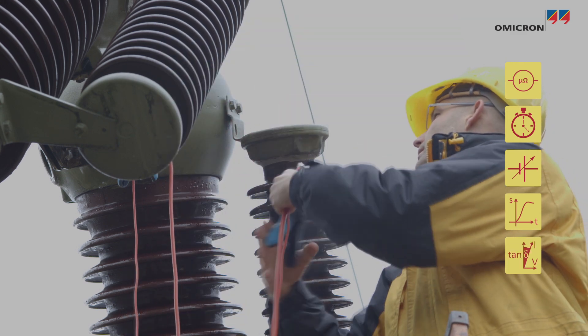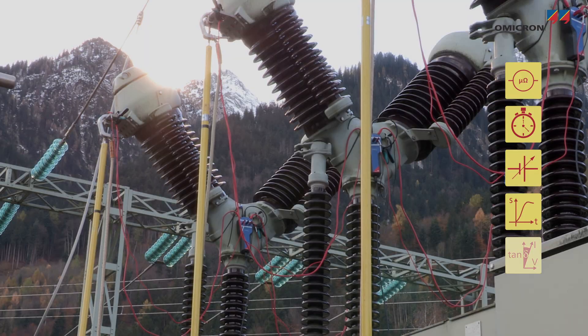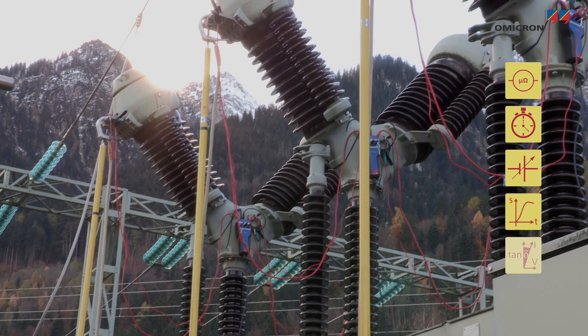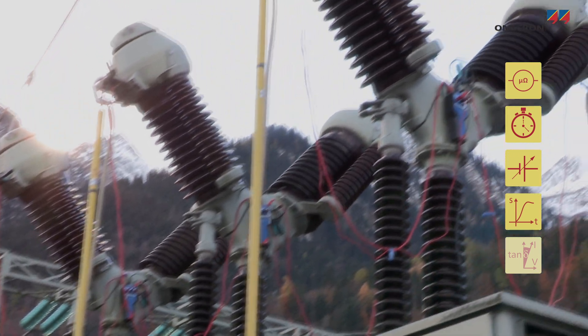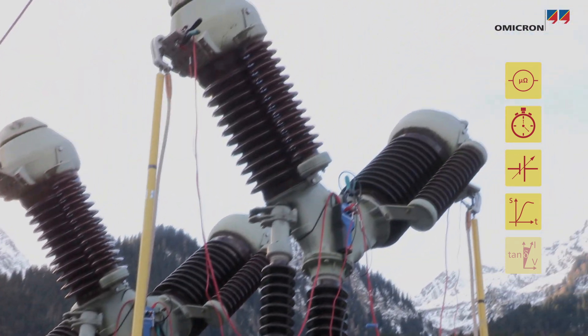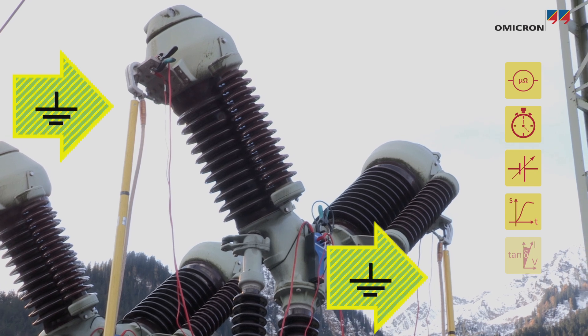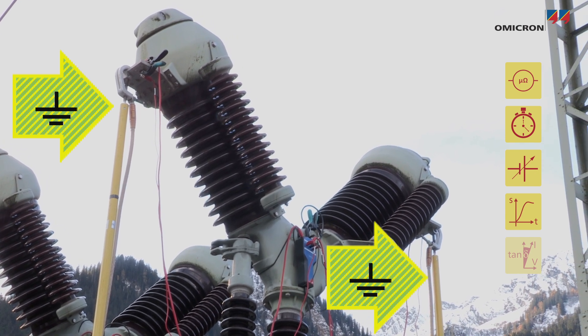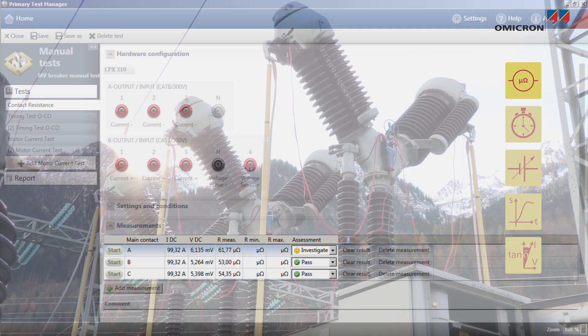In order to ensure the proper operation of a circuit breaker throughout its lifetime, diagnostic tests are performed such as resistance, timing, minimum system pickup, travel, and power factor. To achieve the best safety conditions for the test engineer, the circuit breaker should be grounded on both sides during most of these tests.